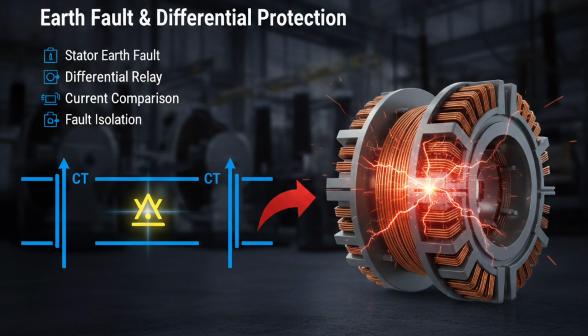Earth faults occur when insulation fails and current flows to ground. Stator earth fault protection detects leakage current to earth. Rotor earth fault protection monitors the field winding circuit. Differential protection compares current entering and leaving the alternator using current transformers. If the two currents differ, it indicates an internal winding fault. Differential relays are very fast and selective. They protect against internal short circuits and are widely used in large generators.